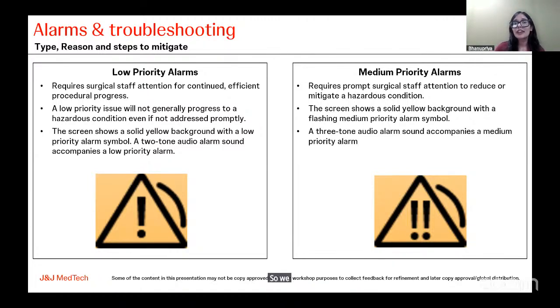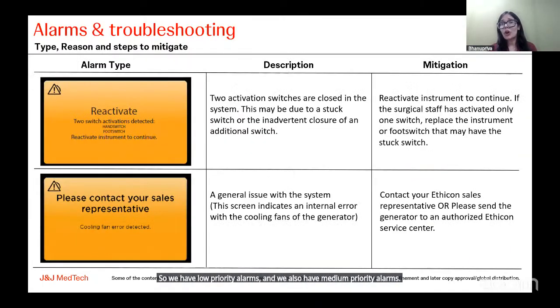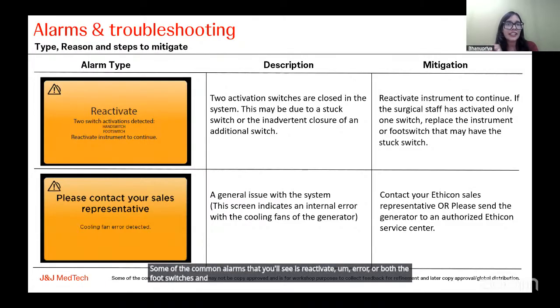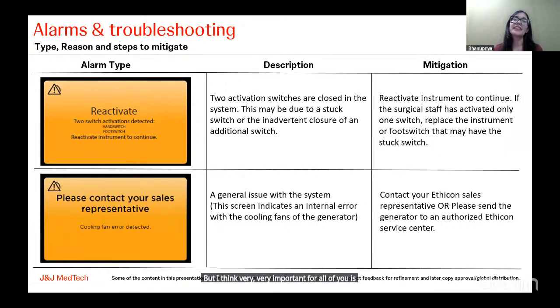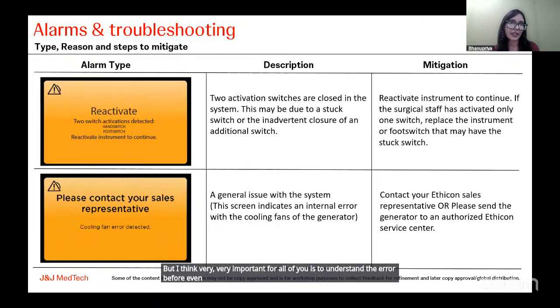So we have low priority alarms and we also have medium priority alarms. Some of the common alarms that you'll see is a reactivate error, when both the foot switches and the hand switches are working simultaneously, so it will pop up an error of reactivation. But I think it is very, very important for all of you to understand the error before even calling a sales rep to say that the machine has stopped. A common feedback that we receive is that the OT technicians call us and tell us that the machine has stopped working, but they don't actually tell us what error is getting displayed on the machine.